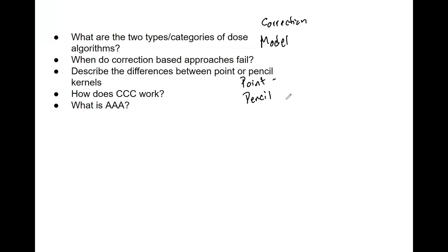Now pencil kernels consider a photon that is incident on a medium and it sums that throughout the medium for the final dose. So it can't handle back or side scatter very well—forward scatter it does okay. But as I mentioned, it is faster, it's still accurate, it's not as accurate as point kernel or Monte Carlo, but it's also much faster than those.